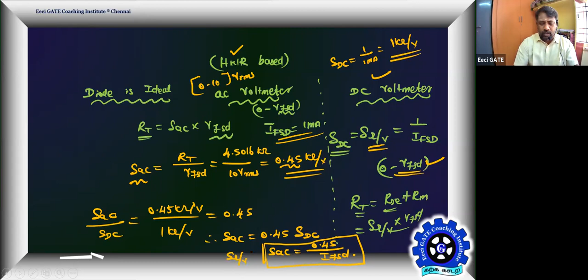But unfortunately, when I use the same meter movement for AC voltmeter design, because it is built by using a half-wave rectifier, it's not a constant current, it's a pulsating current. Because of that, sensitivity decreases to 0.45 kilo ohm per volt. Therefore, SAC by SDC is 0.45 kilo ohm per volt over 1 kilo ohm per volt, so the factor becomes 0.45 roughly. The conclusion is SAC is always 0.45 times that of SDC. Therefore, SAC is 0.45 by IFSD. That's the conclusion. This is still S ohm per volt in AC voltmeters.